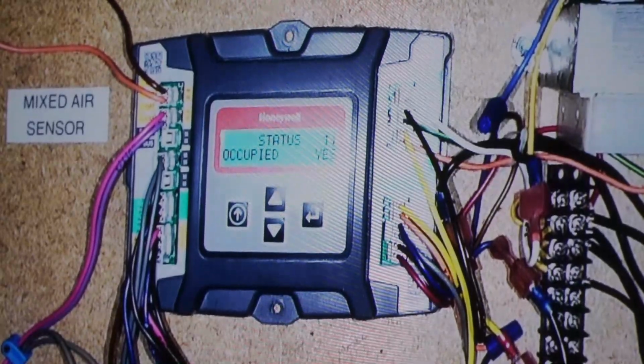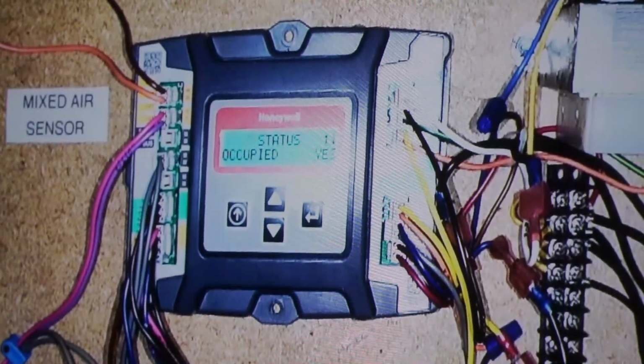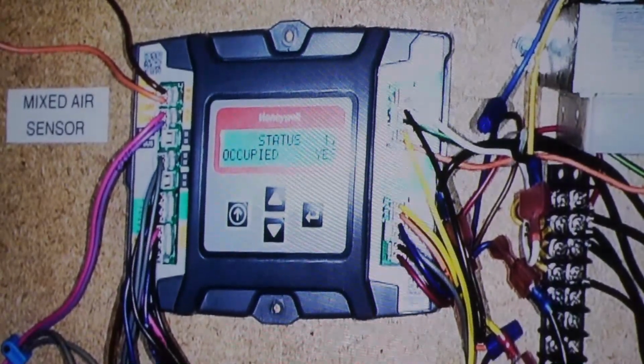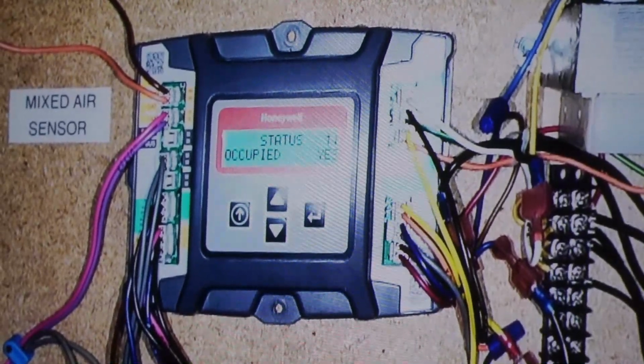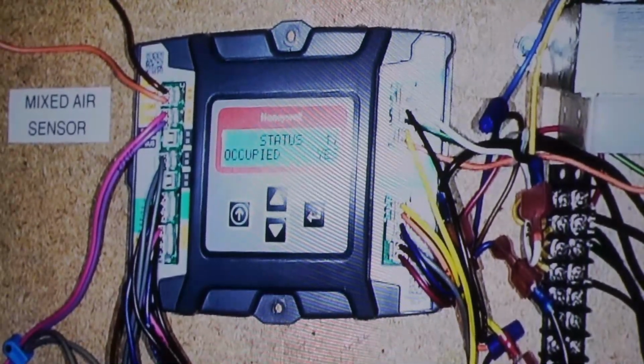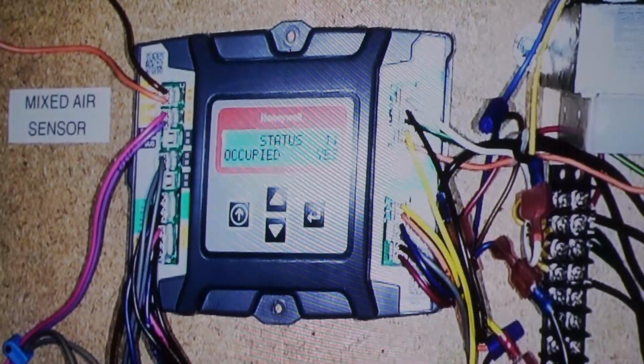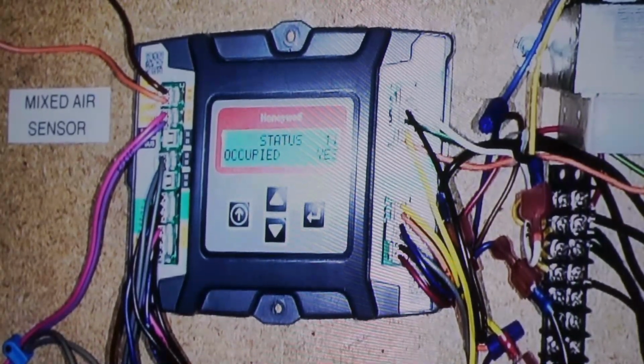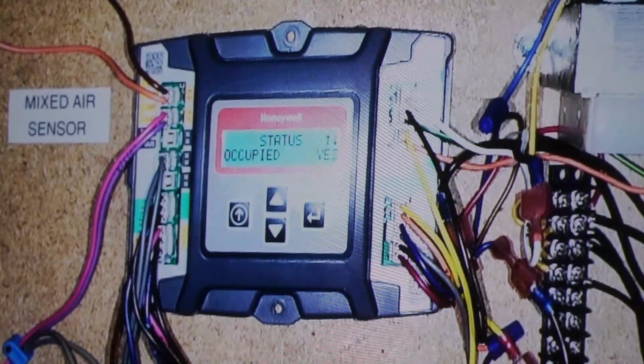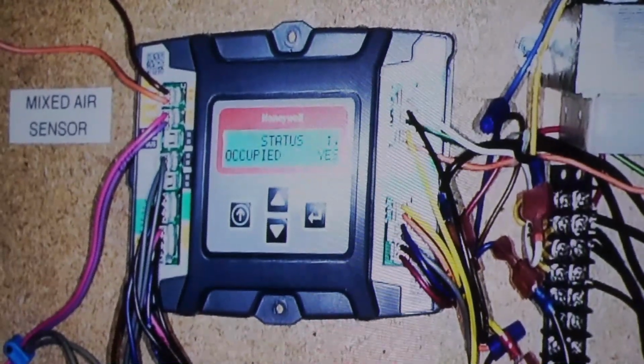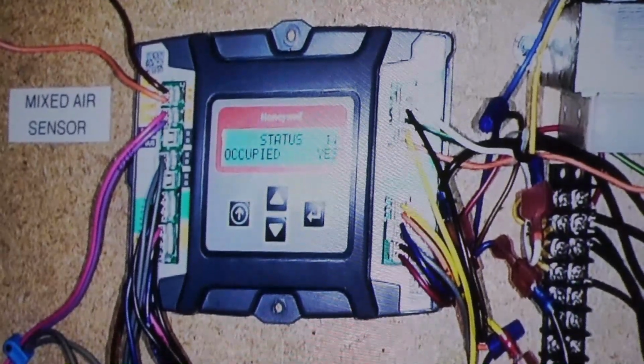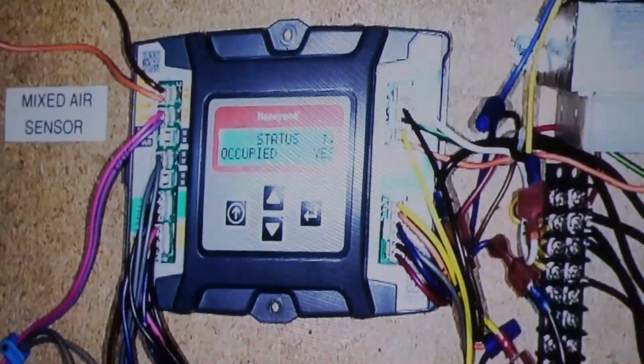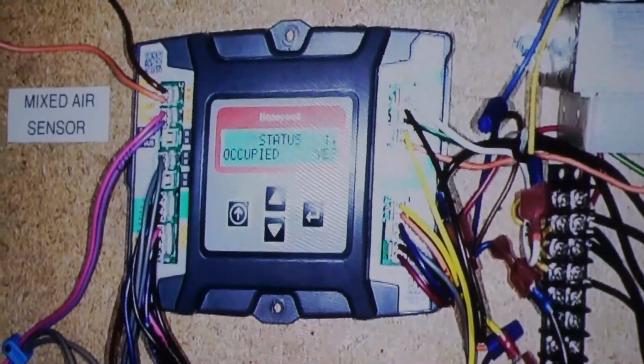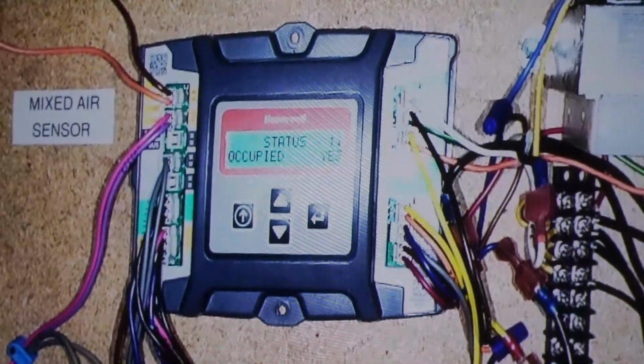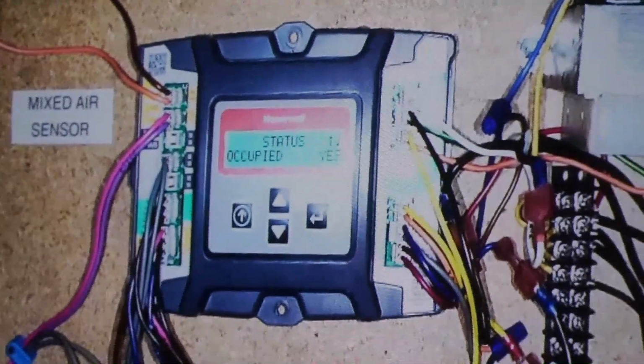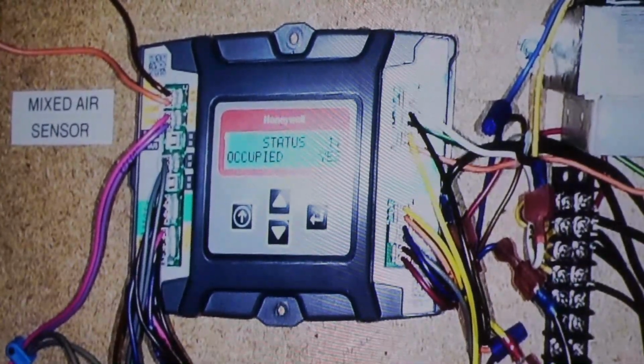Unless I've got a switch, time clock, occupied status on a good commercial stat that I wire in, that I tell the unit when it's occupied or unoccupied. How often do you see that happen? Very, very rare. Nobody's taking the time. I mean, what you're seeing is, it's better than nothing to wire the stat to the terminal strip with all, you know, our 5, 7 wires, whatever it is, and have the fan on during the day and cycle at night.